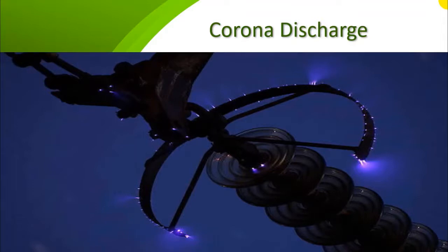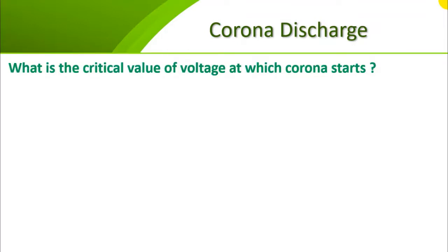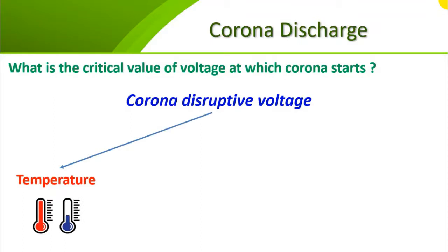So now we can say that corona discharge is a partial breakdown that occurs around the conductor surface due to the non-uniform distribution of the electric field, when the electric field near the conductor surface exceeds the breakdown field of the air. Now, there is an important question to ask. What is the critical value of the voltage at which corona will start to appear? This voltage is called corona disruptive voltage, and it depends on many factors. In our case, in the case of two parallel conductors, corona disruptive voltage depends on factors such as temperature. As temperature increases, corona disruptive voltage decreases, and the possibility of corona occurring increases also. Also, corona disruptive voltage depends on humidity. Humidity increases the possibility of corona formation.